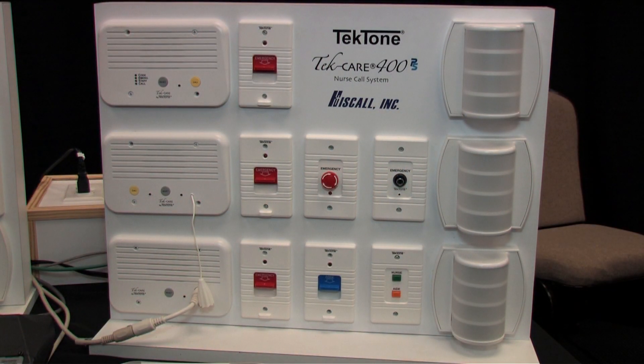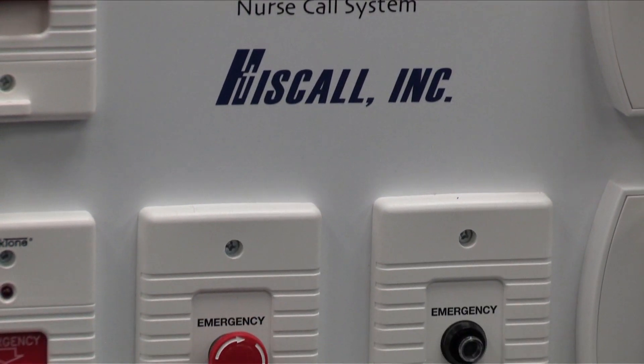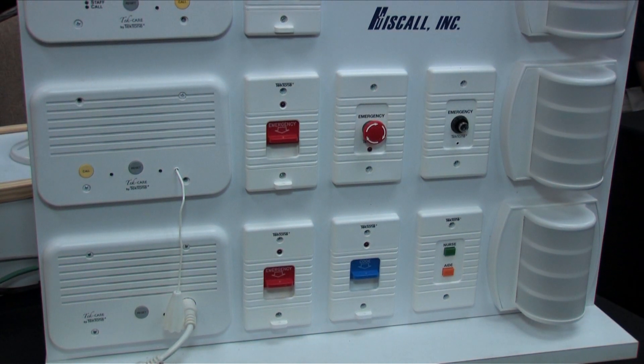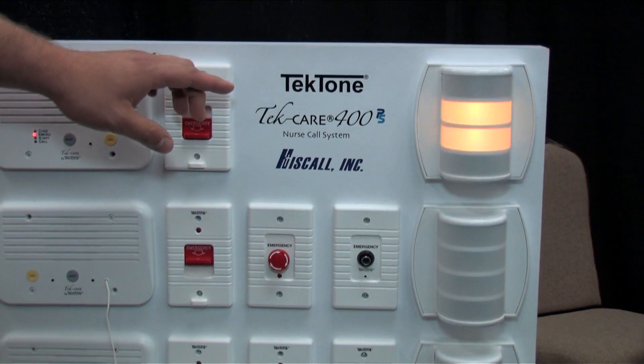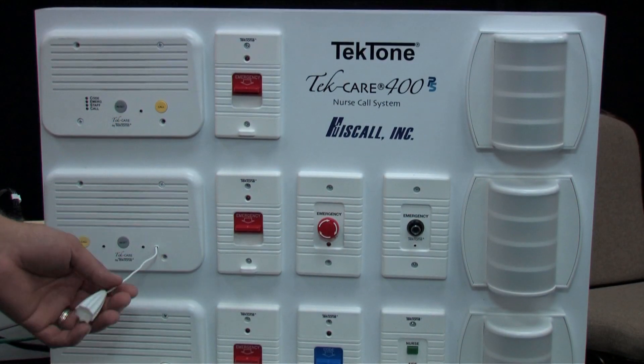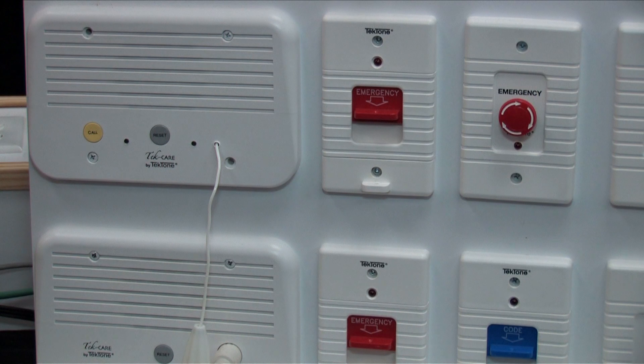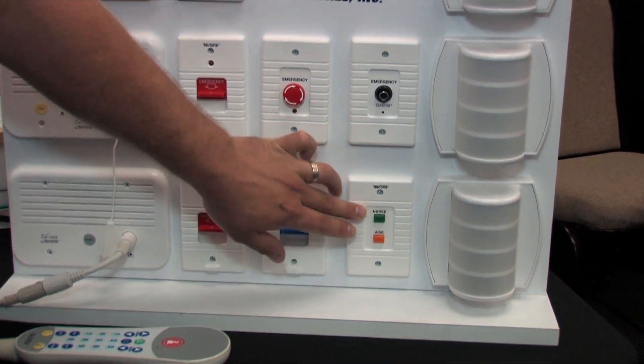The Tek-CARE 400 P5 system is TekTone's newest innovation. This system runs off mainly Cat5 twisted pair. It has a few less built-in features than the Tek-CARE 400 but can do about the same amount. You have slightly better looking stations with this one, still with the same button arrangement. You can program your dome lights to change colors and change the rhythm they flash. With this system they also have a pull cord for check-ins, and a two-button room station to call either an aide or a nurse.